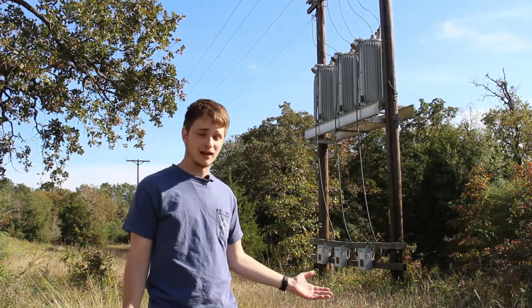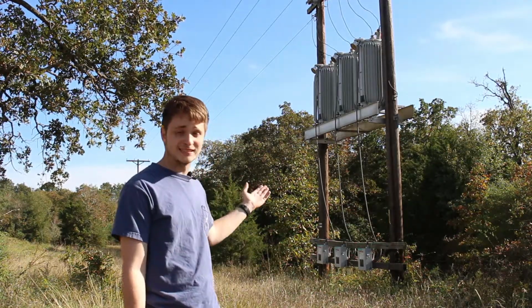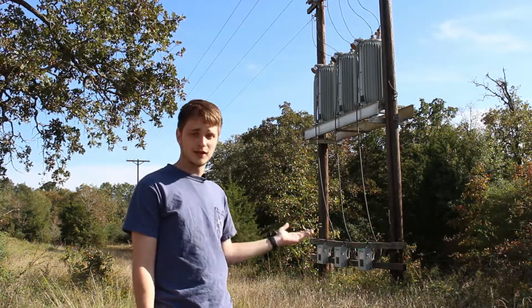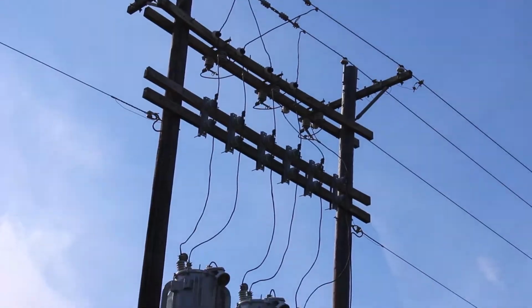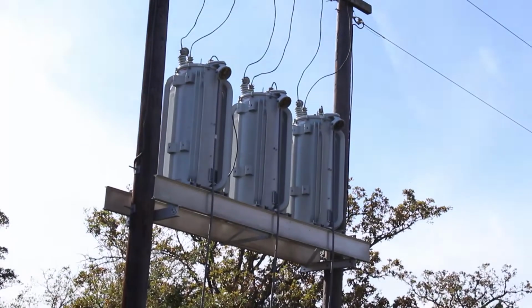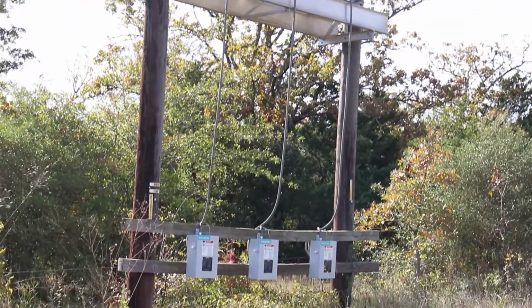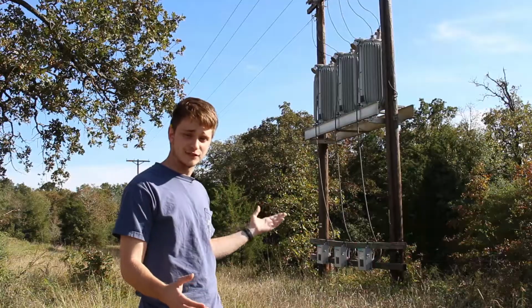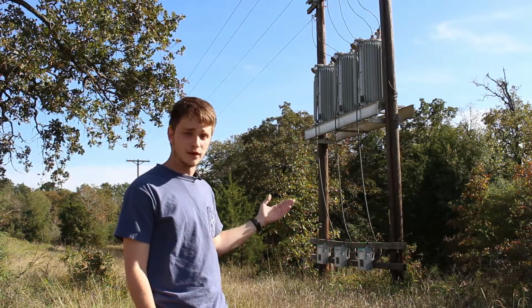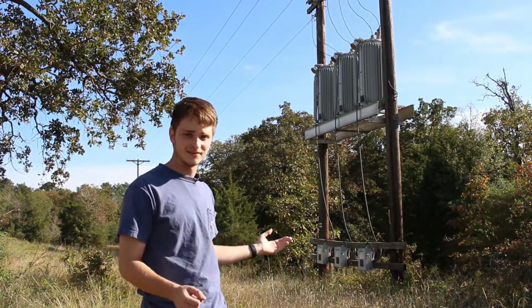As you're also driving on the highway, you might see voltage regulators in series with the line. They are essentially transformers with tap changers to adjust the voltage of the feeders. These are used because over long distances the voltage will drop, and these compensate so that the voltage at the receiving end is what is expected from the sending end.